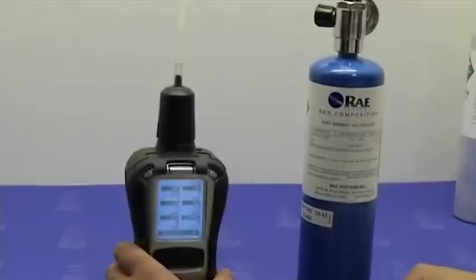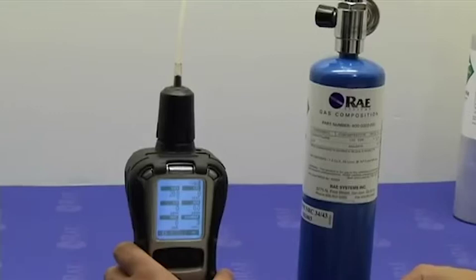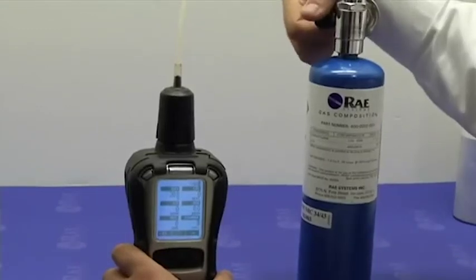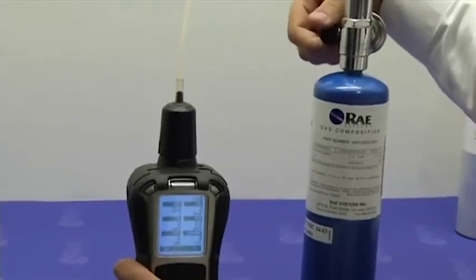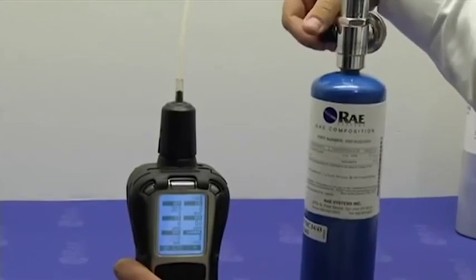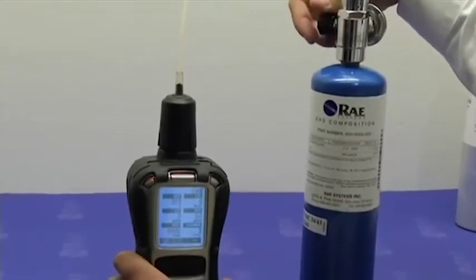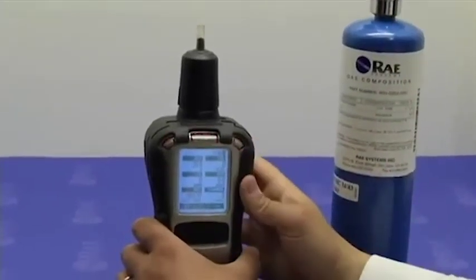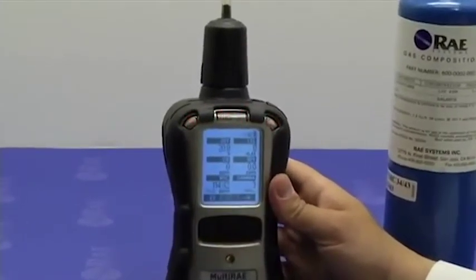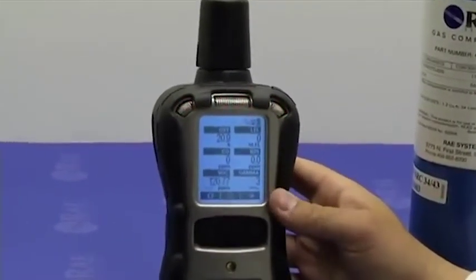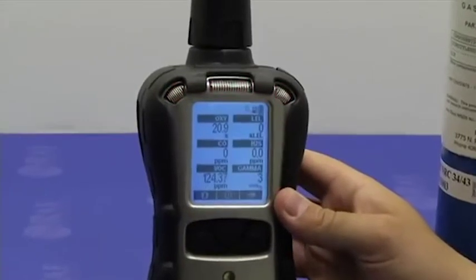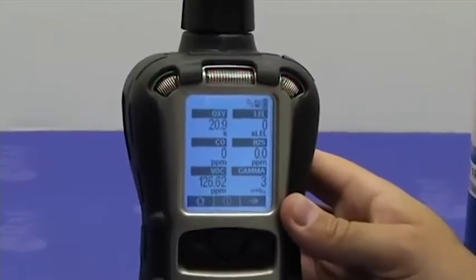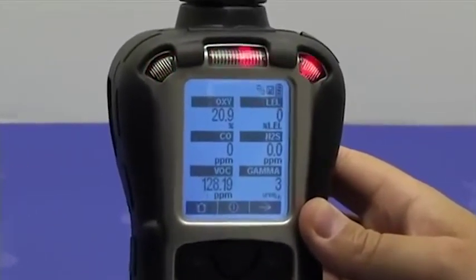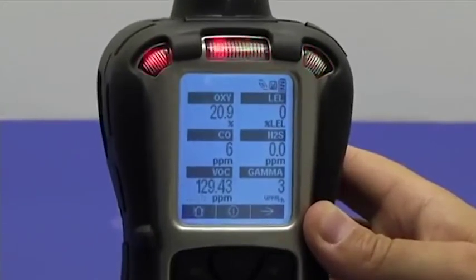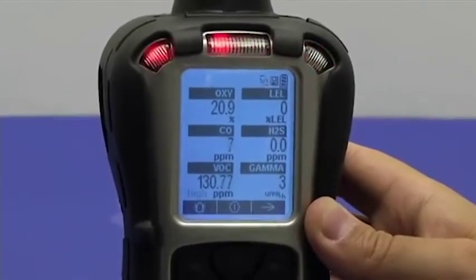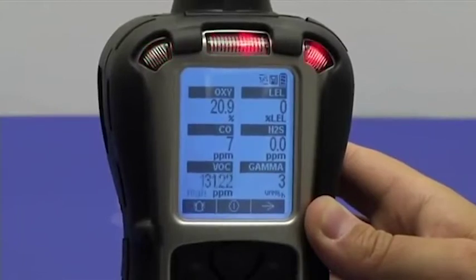Next, I'm going to bump test the PID sensor by exposing it to isobutylene gas. The sensor is really fast, so it goes into alarm really quickly. So I can see that the PID sensor is currently in high alarm. I can feel the vibration alarm, I can hear the buzzer, and I can see the LED lights flashing. So that means the PID sensor also passes the bump test.